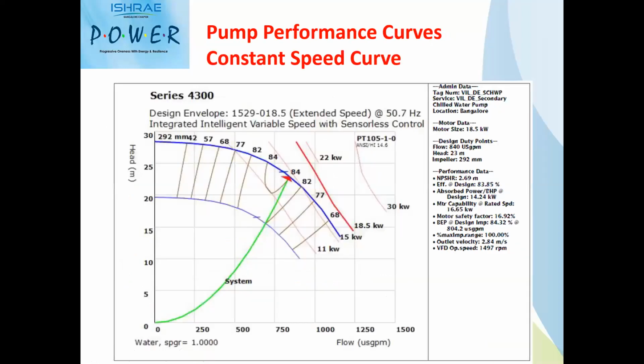So this is a typical pump performance curve for a centrifugal pump. For example, in this case, we have selected a pump of 840 US-GPM at 23 meters head. So this is the duty point at which the pump is selected. These are the efficiency curves. This is the pump performance curve. This is the minimum diameter of the curve. This is the maximum diameter of the curve. These are the power curves.